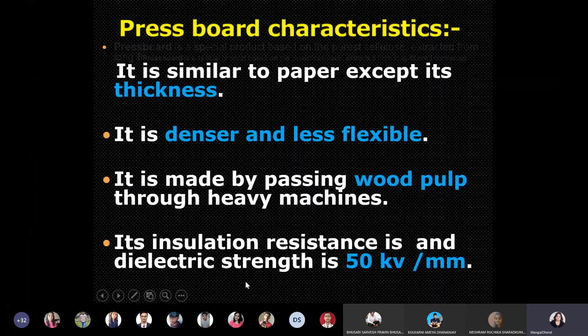So where are these pressboards used in applications? Already I told you, transformers and rotating machines mainly. They are used as conductor insulation. Conductor insulation means across the conductor you can use it, over the winding, in between the different layers of winding. Coil insulation you can use, means one coil, primary coil, secondary, you can use this pressboard. Backing of mica insulation. Mica is also insulation, but if you want to back it, means add a layer, you can use it. Manufacturing of varnish cloth is also there.